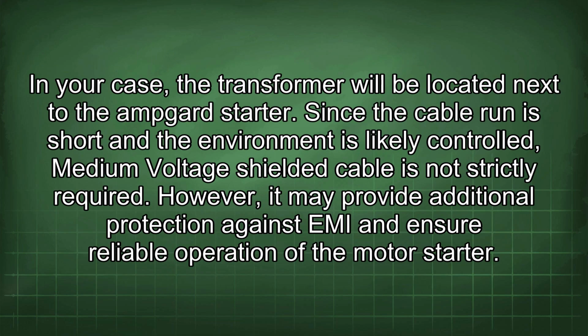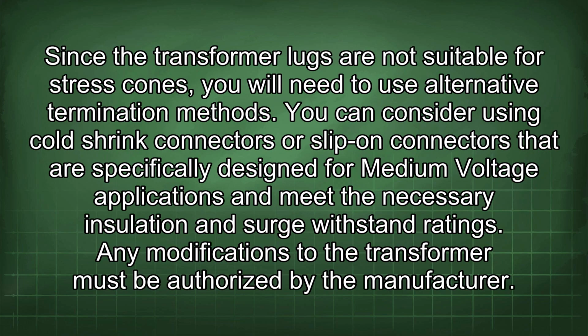In your case, the transformer will be located next to the Ampgard starter. Since the cable run is short and the environment is likely controlled, medium voltage shielded cable is not strictly required. However, it may provide additional protection against EMI and ensure reliable operation of the motor starter. Since the transformer lugs are not suitable for stress cones, you will need to use alternative termination methods. You can consider using cold shrink connectors or slip-on connectors that are specifically designed for medium voltage applications and meet the necessary insulation and surge withstand ratings.